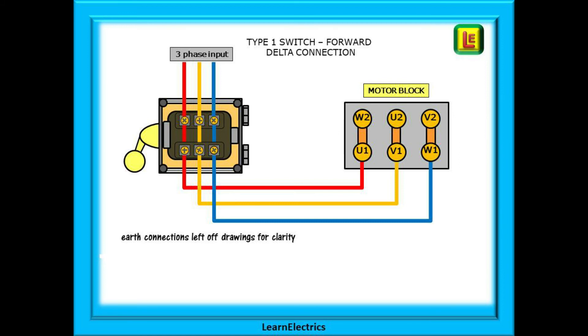In the forward position we have the same supplies to the motor. L1 to U1, L2 to V1, and L3 to W1. And in reverse L1 to U1 again, L2 crosses over to W1, and L3 crosses over to V1. Just to reiterate, make no changes at the motor block. Leave everything as it was. The switch does all the hard work for you.